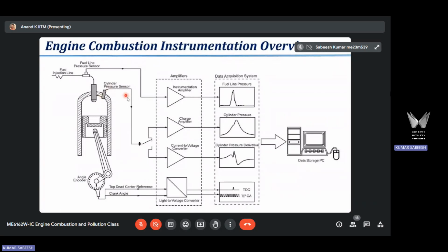Okay, the output from the sensor goes to an amplifier, a charge amplifier. The charge amplifier does two functions. It has an inbuilt filter which will filter out unwanted or noise signals. It also amplifies the signal that comes out of the sensor. The output signal from the pressure sensor is of very low magnitude. The amplifier amplifies that low magnitude signal, and then transfers it to a data acquisition system.